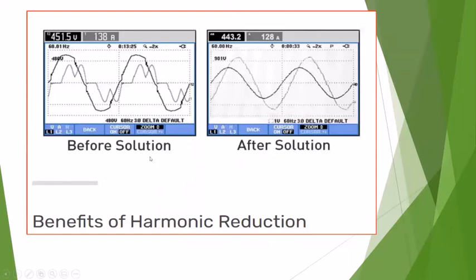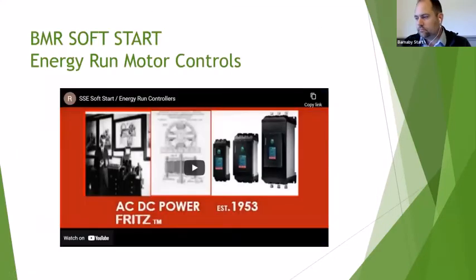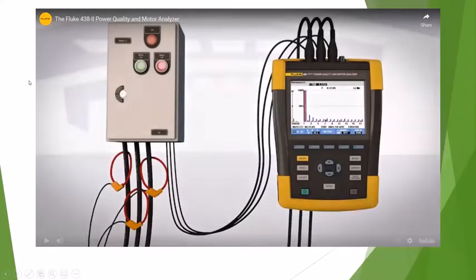So this happened to be a test that was done before with the meter. And you can see this is the voltage waveform, and then this was the current waveforms that we're feeding. And you can see after we put the filtering in how it cleared it up. And so again, your voltage then was much more stable, and your current was basically balanced out. So from doing that, you can see it was 451 volts RMS. The same load was 443 and 128 amps. So if you just do the amps times volts and then times the power factor, which on this was pretty close to unity, there was roughly a 10 kilowatt reduction just from noise. And so that's where your power quality is very important, and it will make a big difference on your ultimate power bill.